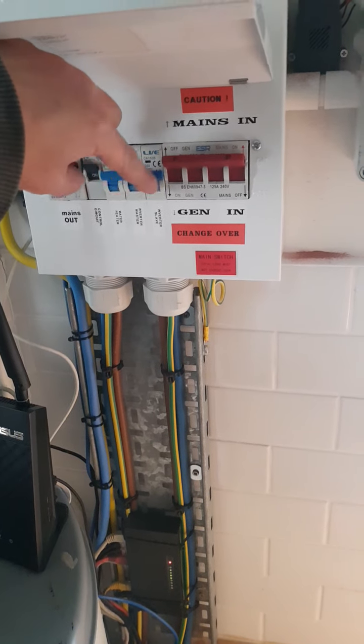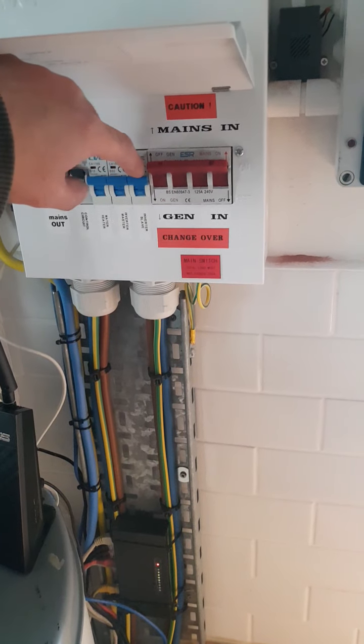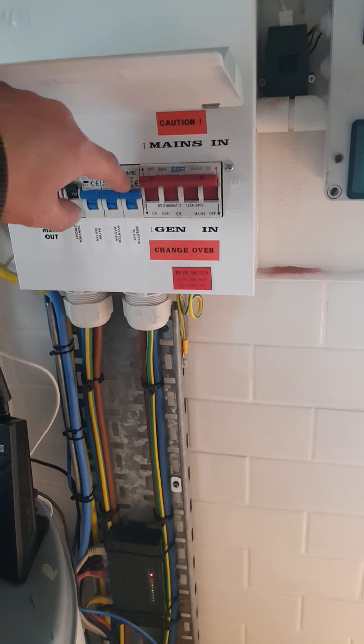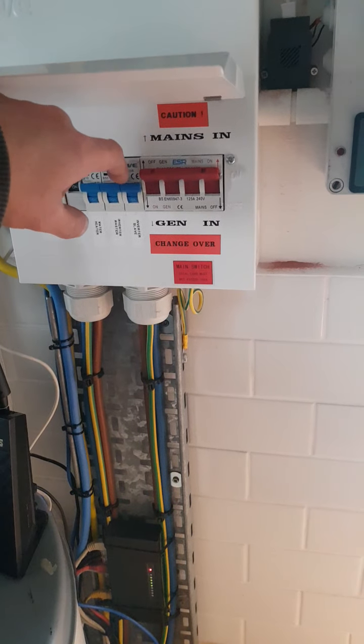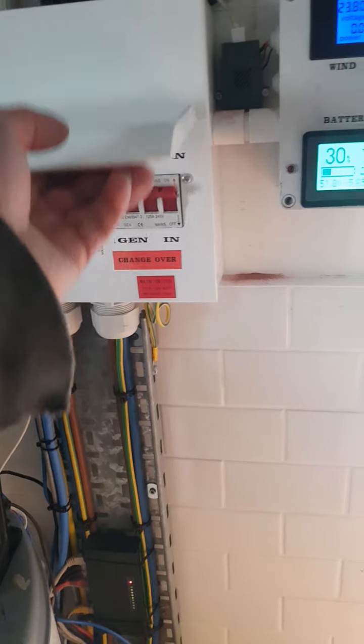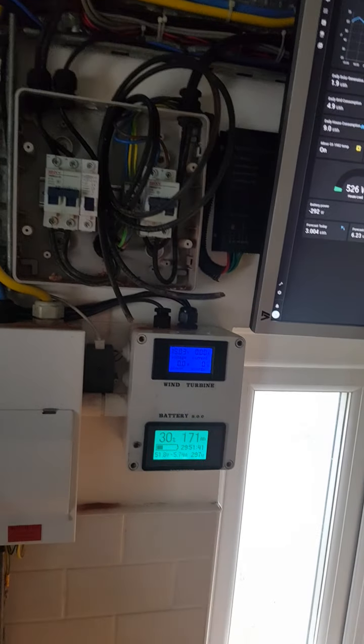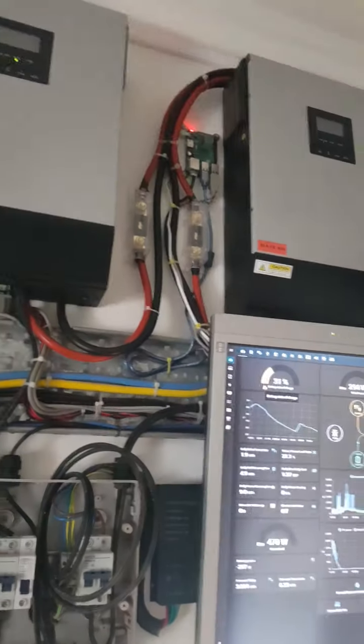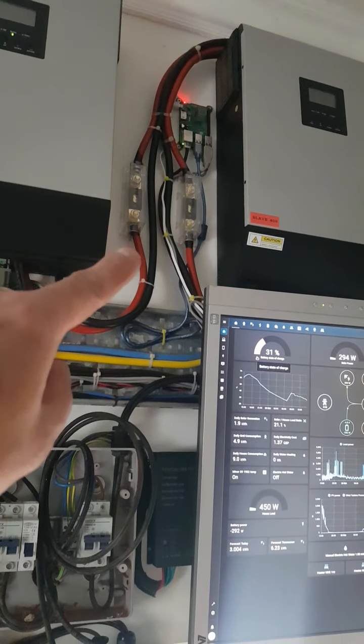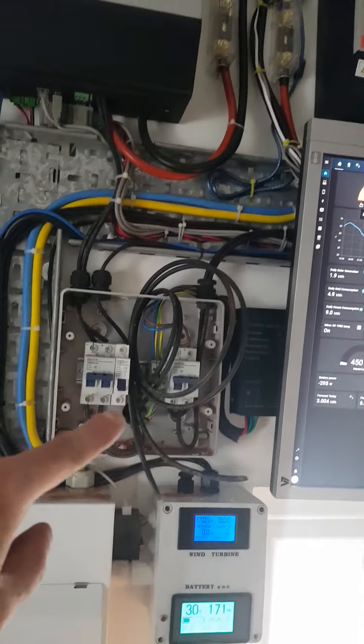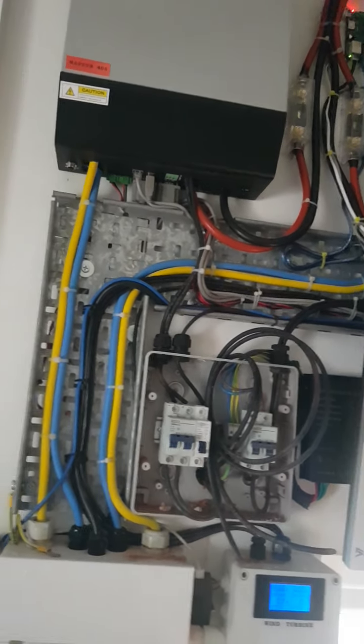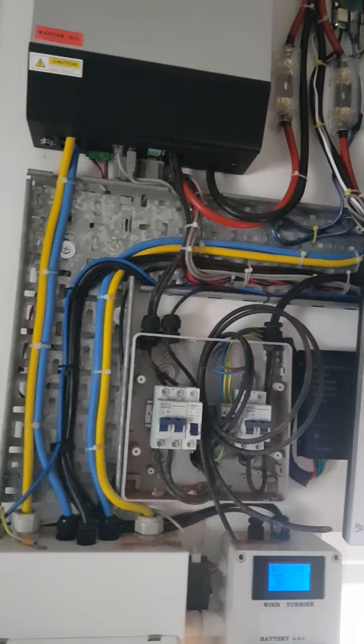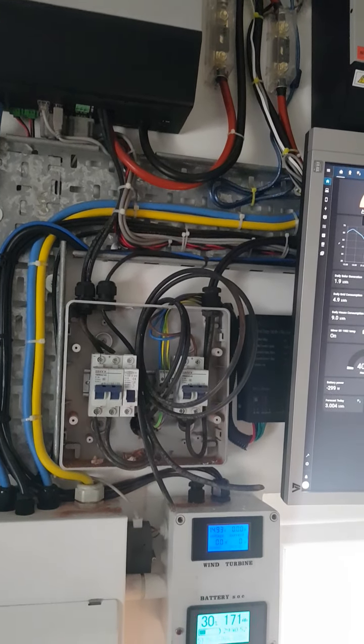And then these are just for your individual inverters, so if there's a problem with the inverter itself you could disconnect it from the AC - that's AC in, from your grid to the inverter. Then you could disconnect it from the battery, just pull the fuse, and also disconnect it from the solar if it's connected. That would then isolate it if you need to do just one or two or whatever you need to do.